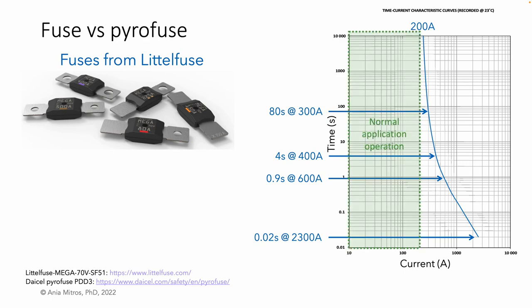This means that our application is okay for any length of time for any current below 200 amps. And the fuse will open for any combination of time and current to the right of the blue fuse curve. Consider the in-between. There is a range of currents for which the fuse will open only after the current has persisted long enough. This poses some design challenges. Though our system may be designed to withstand 200 amps, in some cases it may be subjected to higher currents for long enough to be concerned about collateral damage.